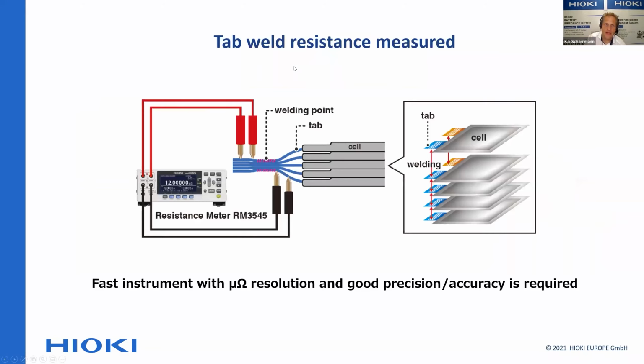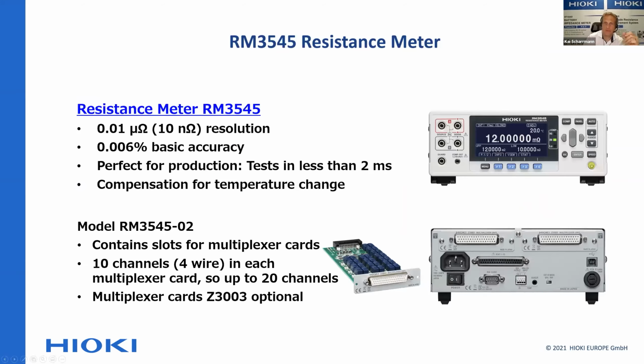So what is the method of that? It is just a very, very traditional 4-wire measurement method. It's a DC measurement method, and it simply goes over the tab welds, goes over the contacts, and tests them in micro-ohms resolution, to test the weld quality. The interesting thing about the product that we're talking about when it comes to that is a resistance meter called RM3545. The interesting part about that, it is actually already made to be integrated into a productive or production environment.